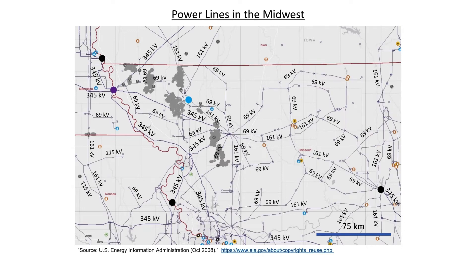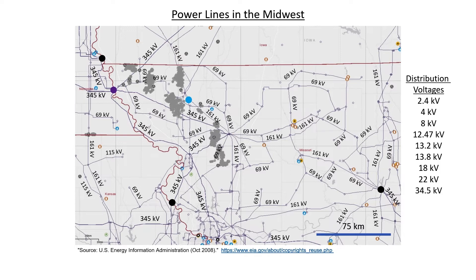Let's now take a look at some of the lower voltage lines. You're now seeing all the power lines with voltages down to 69 kilovolts. These medium-sized power lines are mainly at 161 kilovolts and 69 kilovolts. Of course, this is not all the power lines in the region — there are a number of smaller distribution voltages. The three most common distribution voltages in this region are 4 kilovolts, 12.47 kilovolts, and 13.2 kilovolts. Those three voltages represent the last leg before you reach the pole transformer that delivers plus and minus 120 volts to the customer.